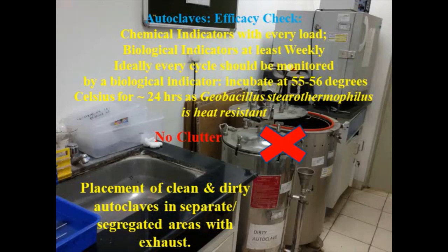It is very important to check the efficacy with chemical indicators with every load and biological indicators once every week. That is the national recommendation, and after that the biological indicator should be incubated at 55 to 56 degrees Celsius. And the lab should ensure that there is no cluttering in the autoclave room. The clean and dirty autoclaves should not be placed side by side because there may be a chance of cross contamination. Steam is generated here, so this room should be fitted with an exhaust. Ideally, the lab should have two different rooms where the clean and dirty autoclaves are placed. And if they are placed in the same room, they should be segregated by a barrier, so there is no chance of cross contamination.